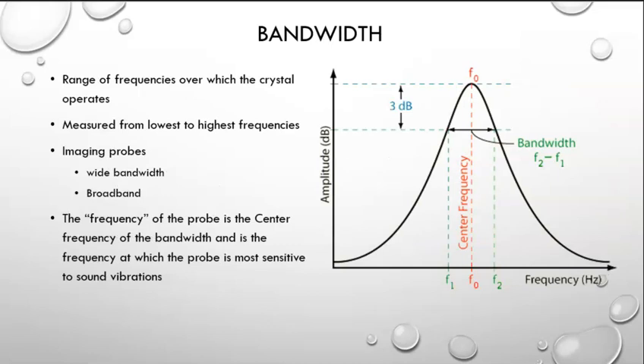When we pick up a transducer and we're going to image something, typically an abdomen, you're going to image it around what we say is 4 megahertz. Go to any of the machines in the lab, pick up an abdominal transducer, and it'll probably say something like 4 on it. That means that is the center frequency of the transducer. The center frequency of the transducer is where the transducer is the most sensitive. That is the frequency where the transducer is most sensitive to sound touching it. If sound touches it at that frequency, it makes the strongest electrical signal back to the system.